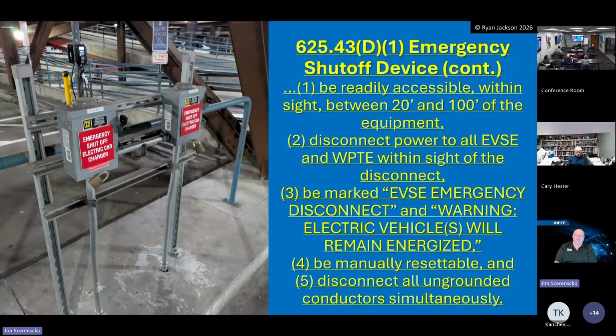A lot of this all falls back on the thermal runaway. Right now, here in Raleigh, if they build a parking deck and they're going to put electric vehicle chargers in that parking deck, the building official will make them put a 4-hour rated firewall if it goes up against another building, because there's no way for the firemen to control these thermal runaway fires. And actually, there's a big push to keep them below a certain level in the parking deck, because the trucks can't get up there to fight them.